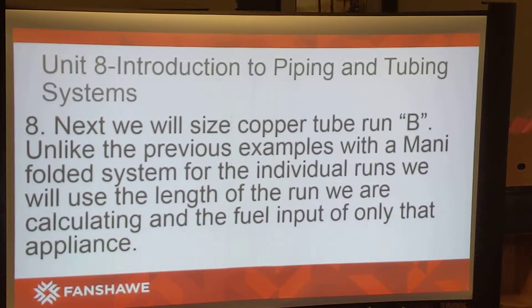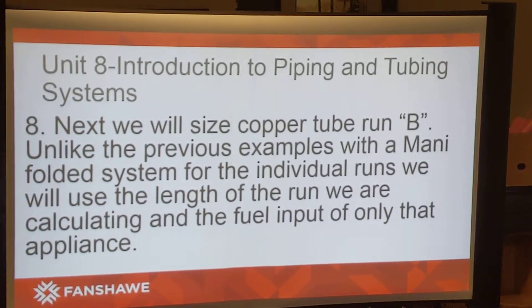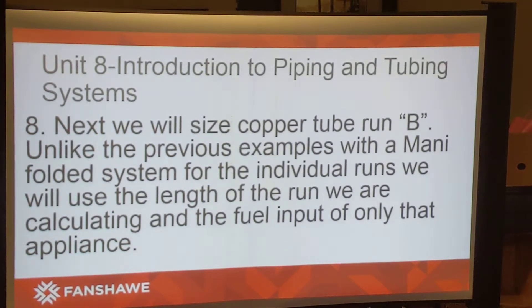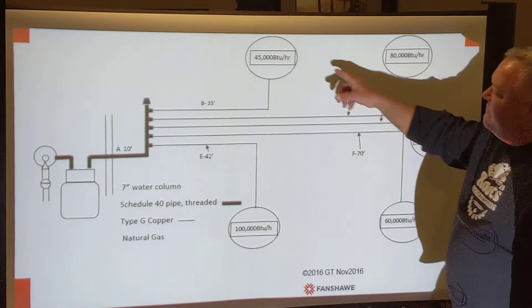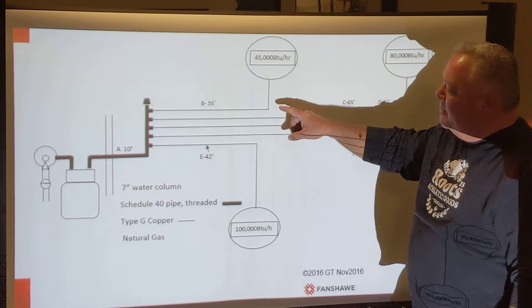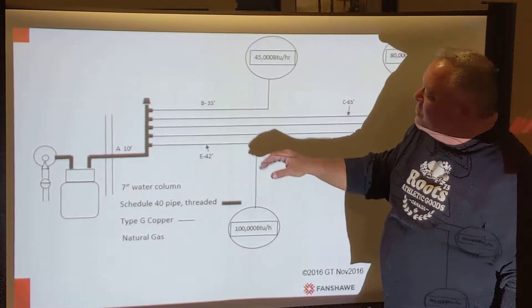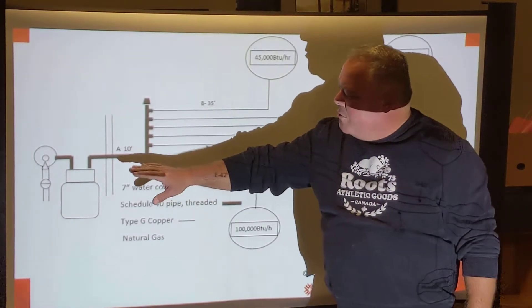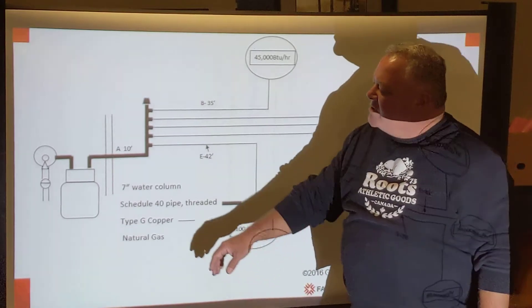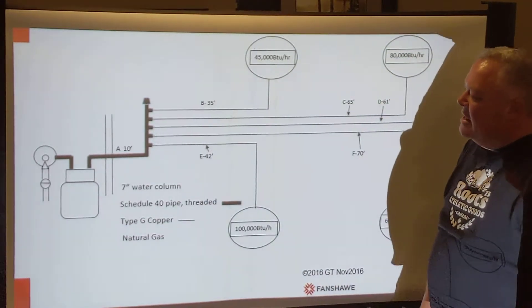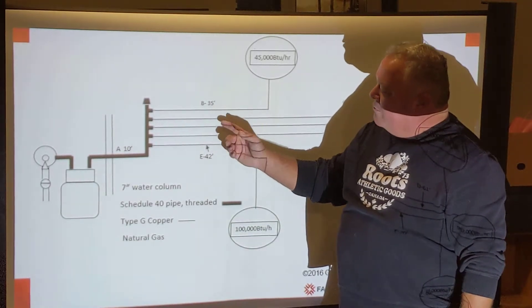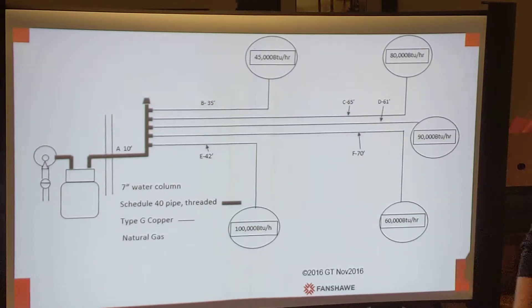Next we're going to size the copper tubing runs, starting on tube B. On manifolded systems, for individual runs we use the length of the run individually and only the input of the appliance on that particular run. For tube B, we have a 45,000 BTU per hour appliance. Tube B has a tubing length of 35 feet, and we always add the 10 feet of schedule 40 pipe since we measure from the outlet of the gas meter, giving us a total measured run of 45 feet.